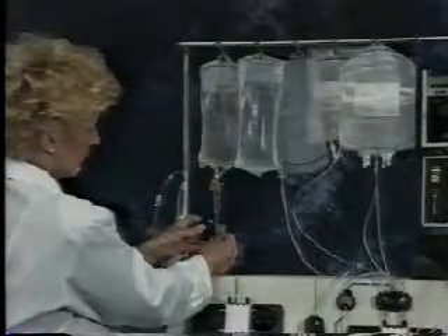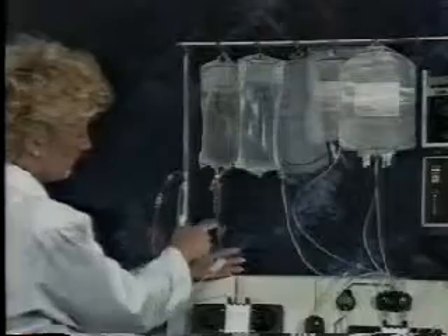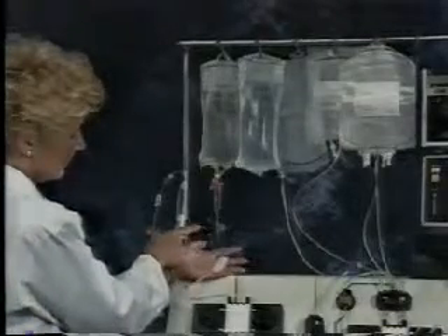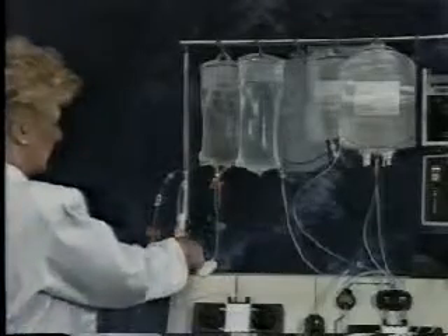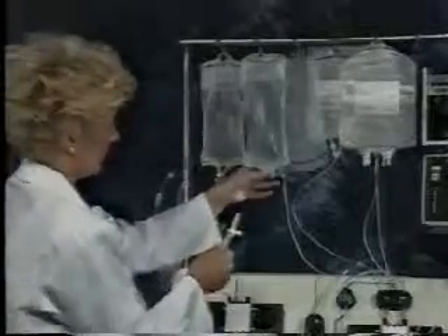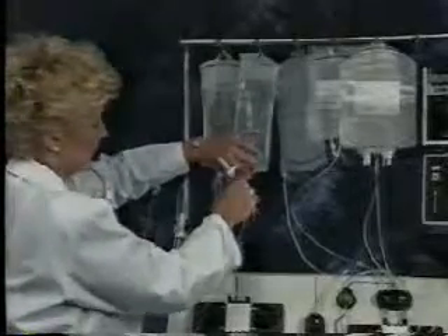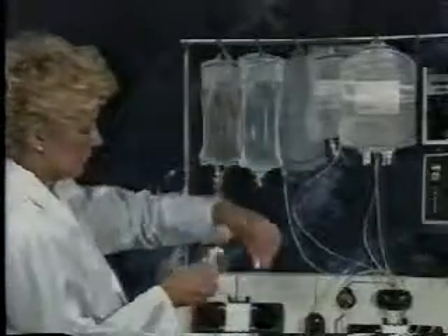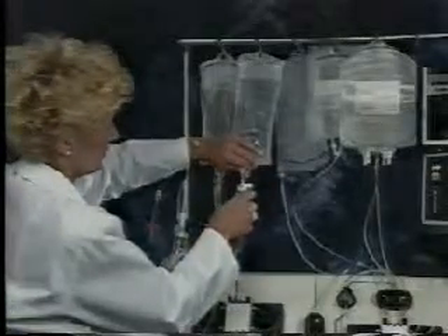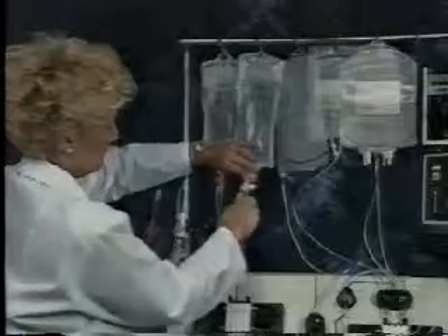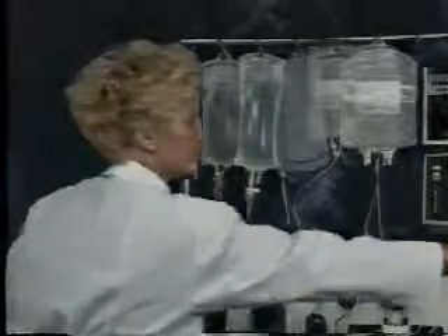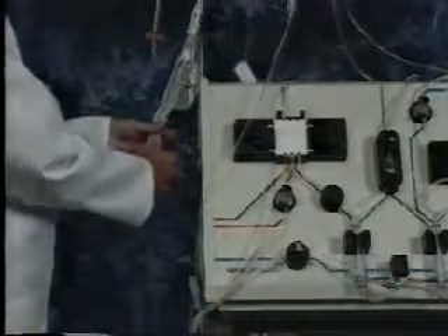Then place the air line in the air level detector. Ensure that the air line is not kinked and the filter is below the AC level detector. Next, connect the access saline line to the saline container and fill the drip chamber 1/2 full. Press the Continue key. The system will then instruct you to open the access saline line. Open the roller clamp on the green access saline line and press the Continue key to prime the tubing set.